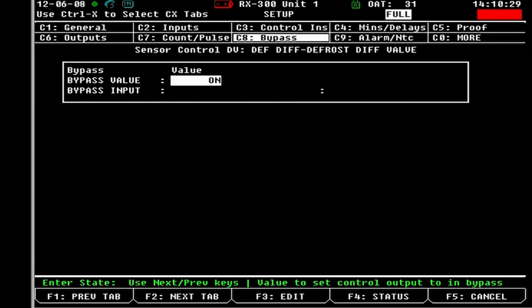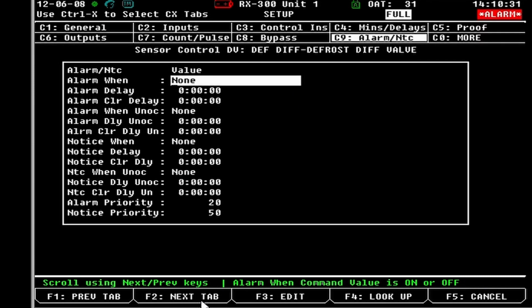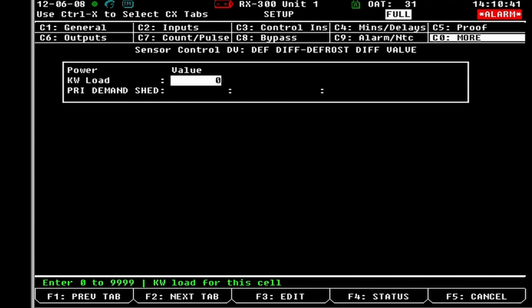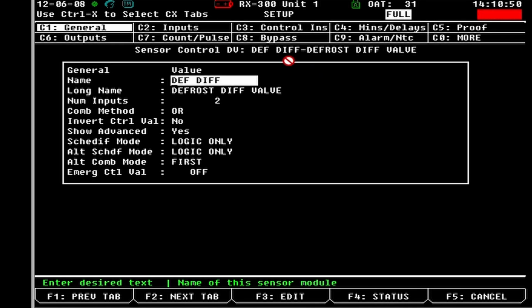So if you go to your next tab, you get your alarms. Just like everything else, the analog sensor control, you got your alarms in here. So all your alarms are in here, whether it's on, it's off, it's an alarm, your alarm priorities. You get the next tab, you got your KW stuff. Like I said, we're not really using this stuff to bump KW. So that's how you do a basic sensor control, digital sensor control.